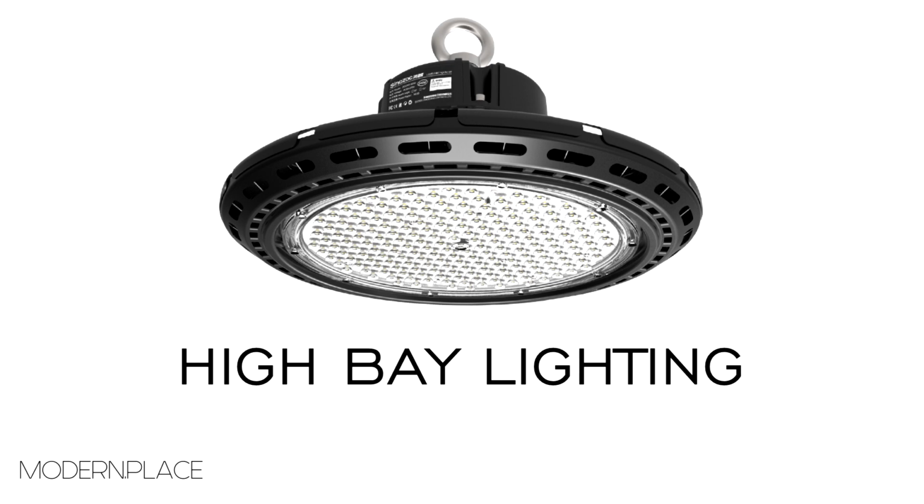And finally, we're going to talk about the total lumens you might or might not need. Generally, for low, let's say 10 to 20 foot high warehouses that aren't special cases where you need extremely bright light, you want to be between 100 and 150 watts on the high bays if they're running at 135 lumens per watt. Because if you place a 240 watt UFO only 14 or 11 feet up, it's just going to hurt your eyes if you look up at it. They're extremely bright, because at 240 watts you're essentially looking at 32,500 lumens with our lighting, and I don't recommend you look. It's like the solar eclipse. Get some eclipse glasses if you're going to be looking at that.